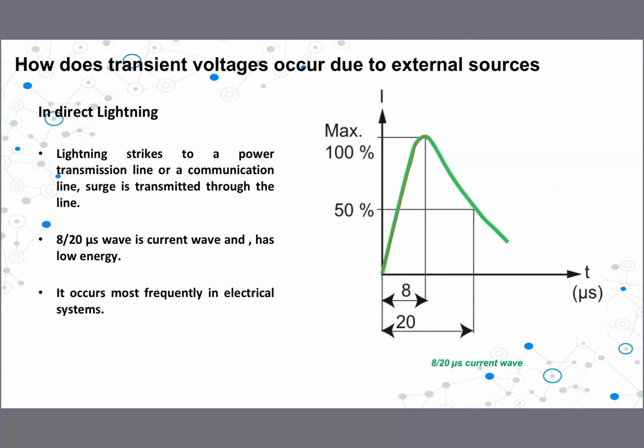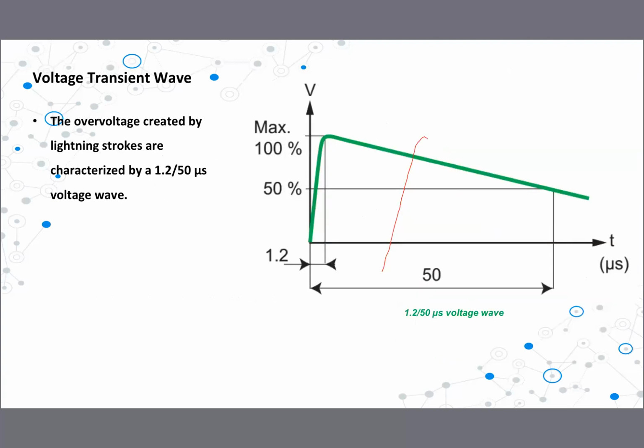So then this is the transient voltage waveform due to indirect lightning, right? This wave reaches its maximum within 1.2 microseconds, and the duration of the wave is 50 microseconds. Therefore it's called a 1.2 by 50 microsecond test impulse voltage waveform. So now we have an idea of what the external sources and internal sources are which cause transient voltages. Let's move on.